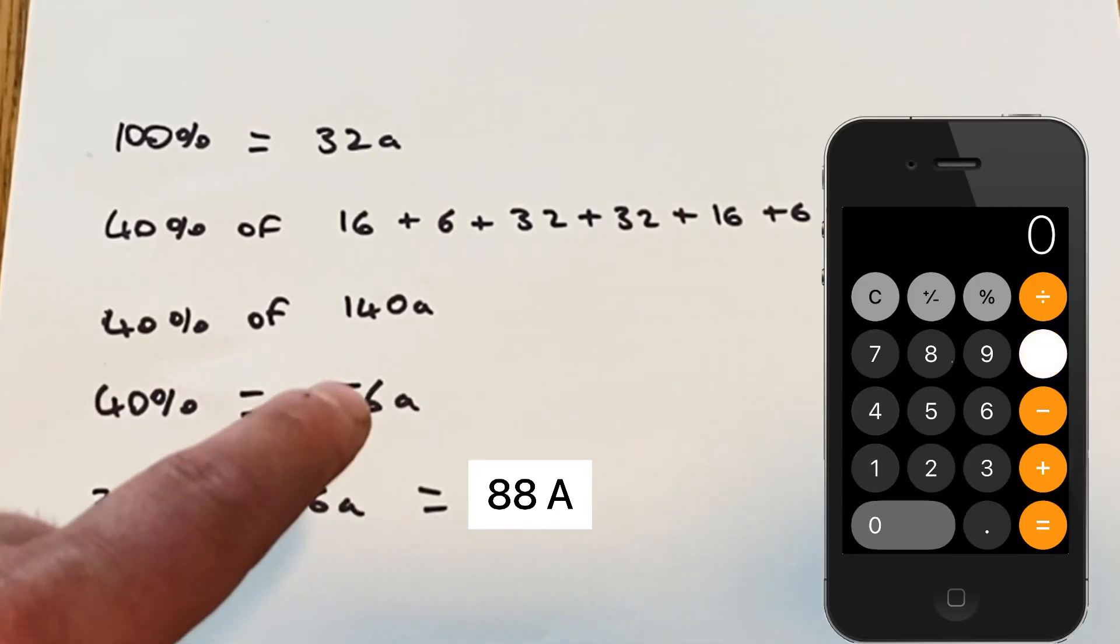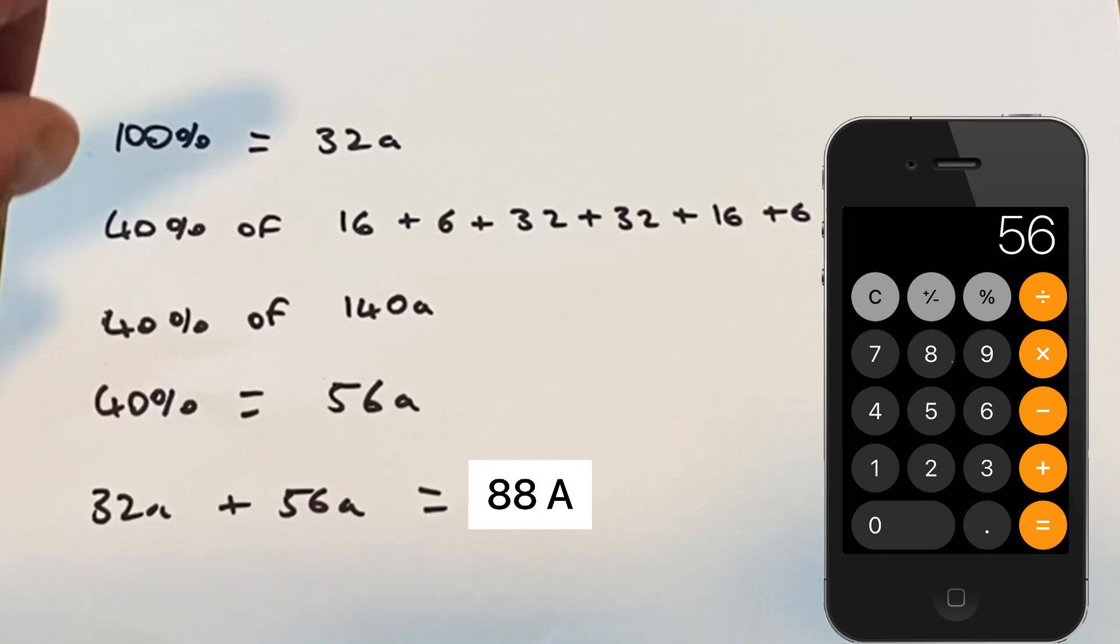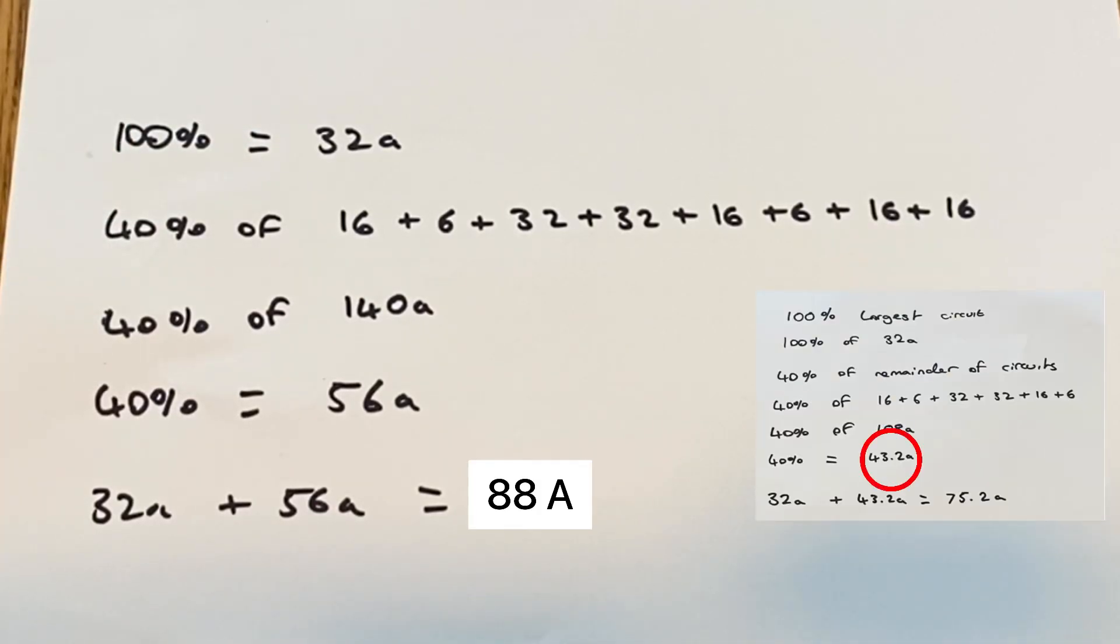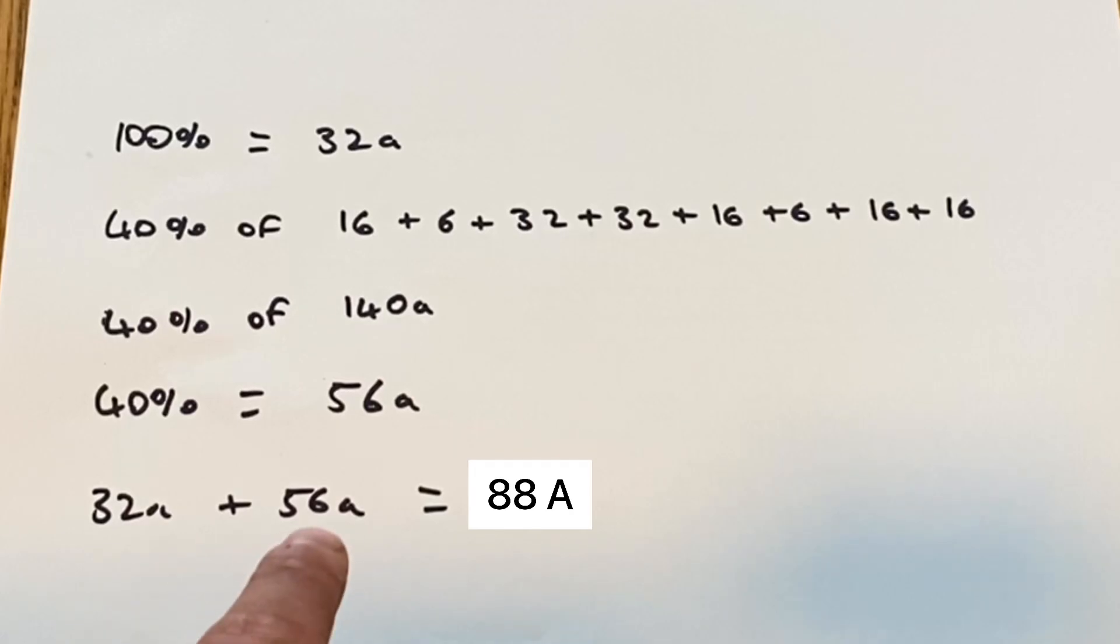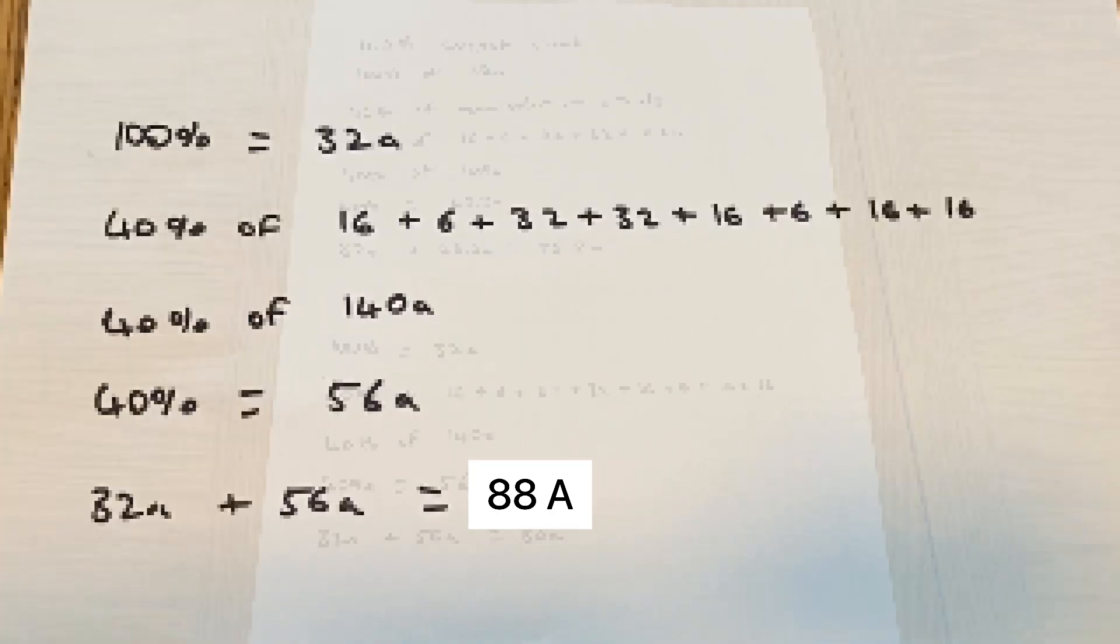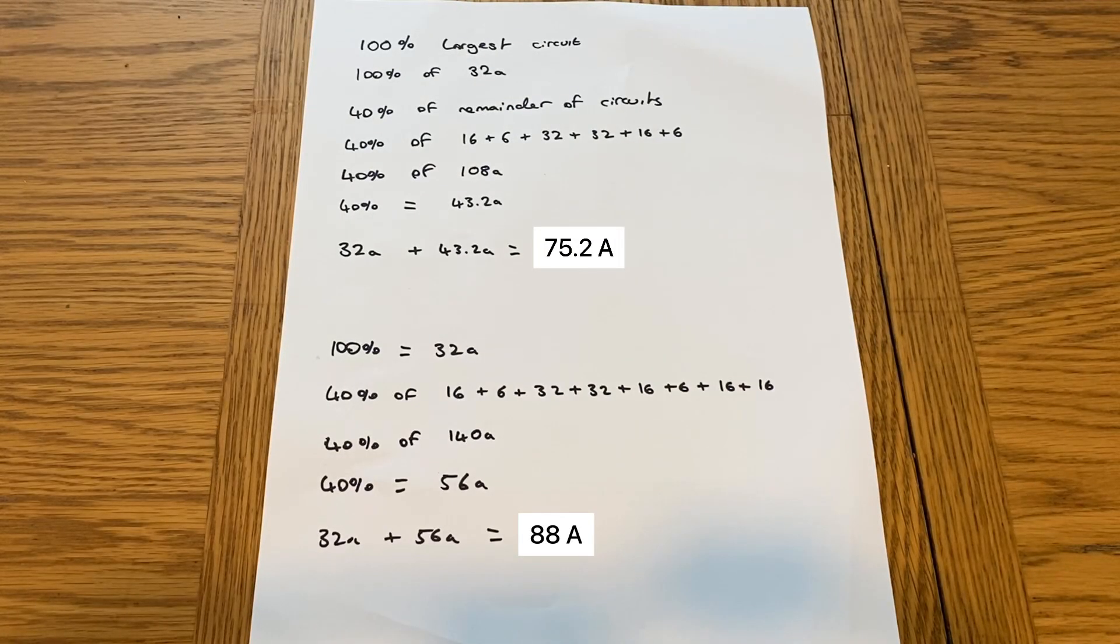We've added two circuits and you can see that it's actually increased from 43.2 to 56. So we add the 32 amps to the 56 amps which actually gives us a maximum demand including our diversity of 88 amps. As you can see it's a nice easy calculation, one you can really do on your phone while you're on site.